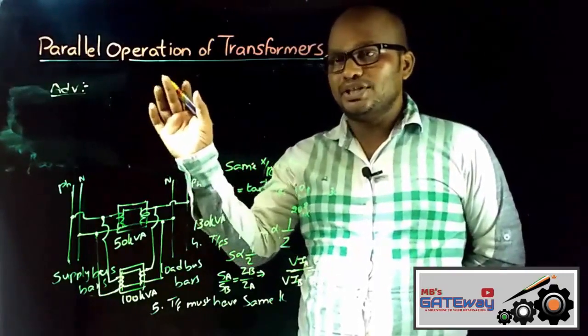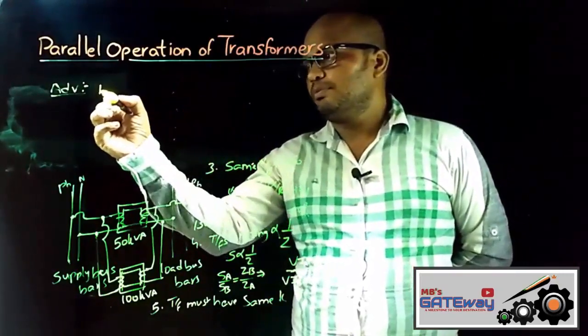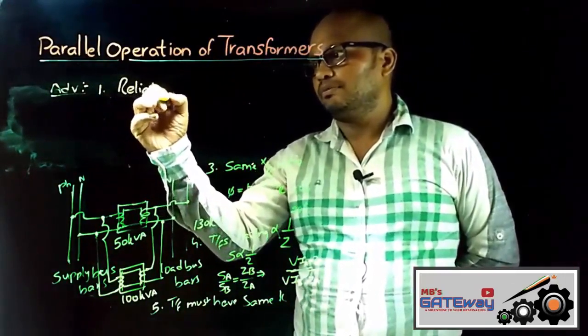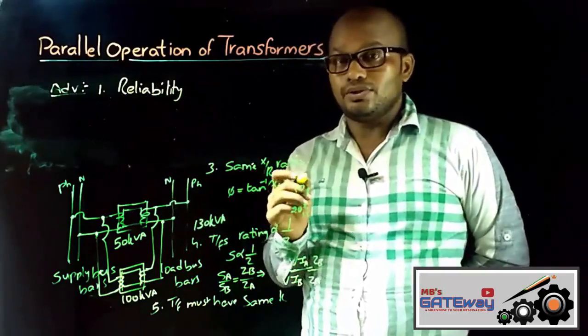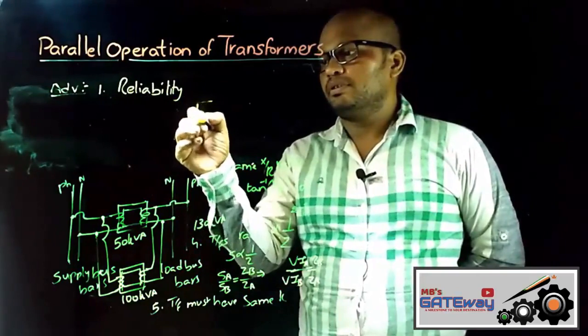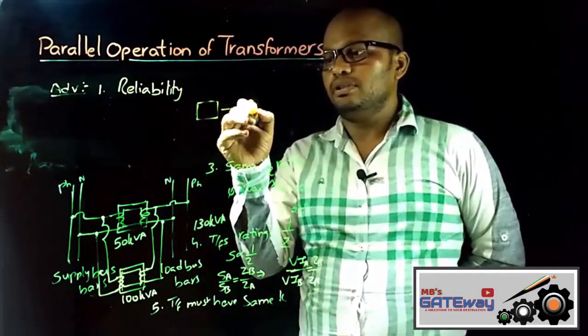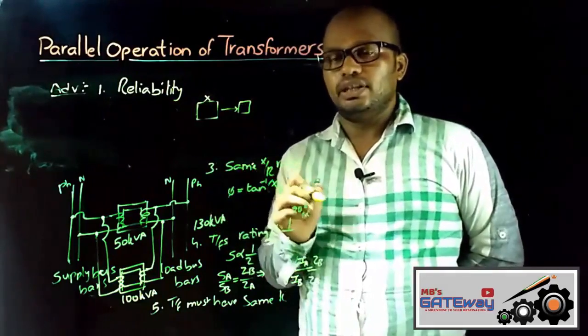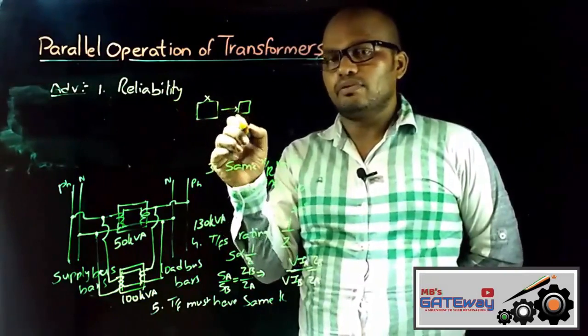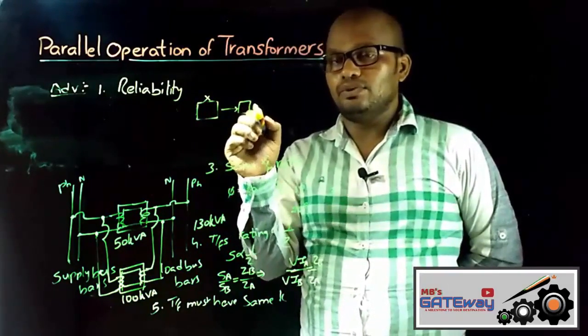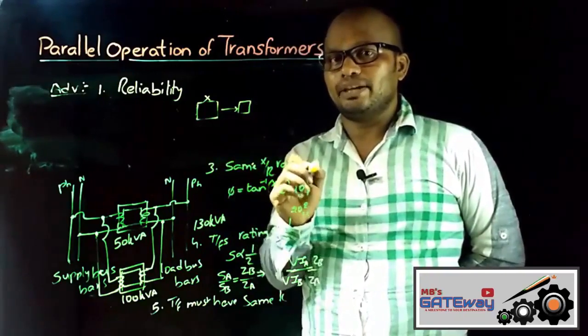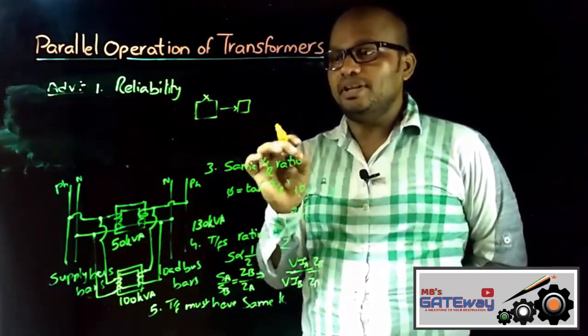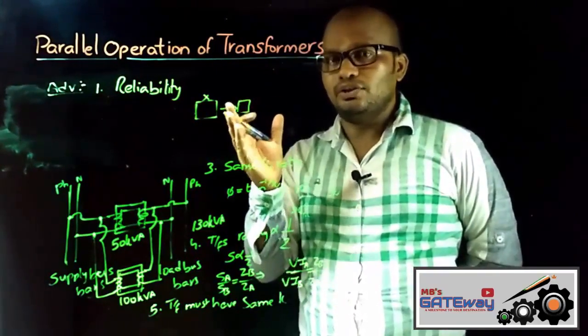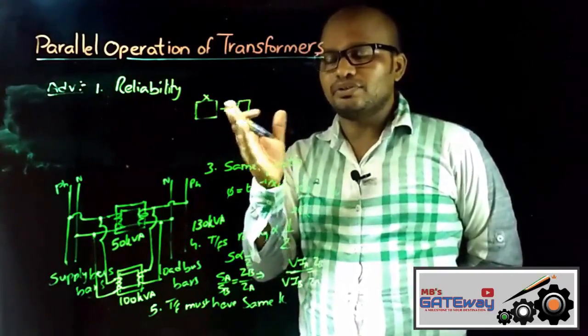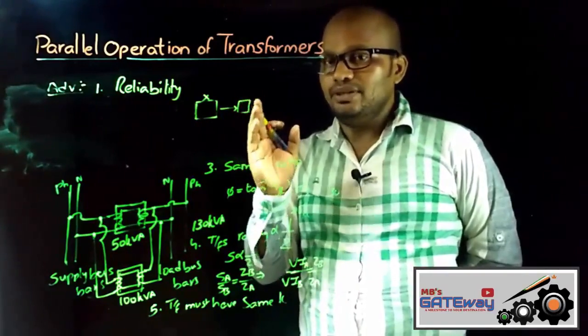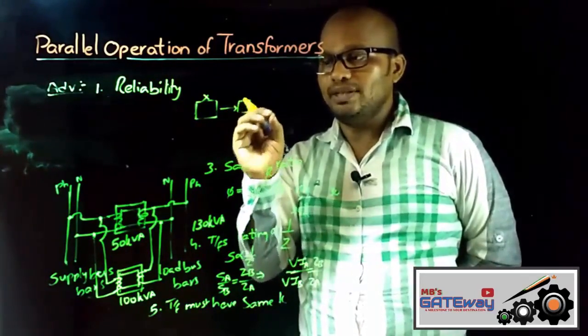And here are the advantages of parallel operation of transformers. The most important point here is reliability. In parallel operation, if suppose a single transformer is supplying power to the load, and due to some unknown reason this transformer fails, then what will happen? The load will no longer receive the supply, which means there is discontinuity of supply. In power systems, one of the important criteria to be maintained is continuity of supply. However good the quality of power supply may be, if there is no continuous supply, what's the use? Therefore, in power systems, along with quality, continuous supply is also an important criterion.